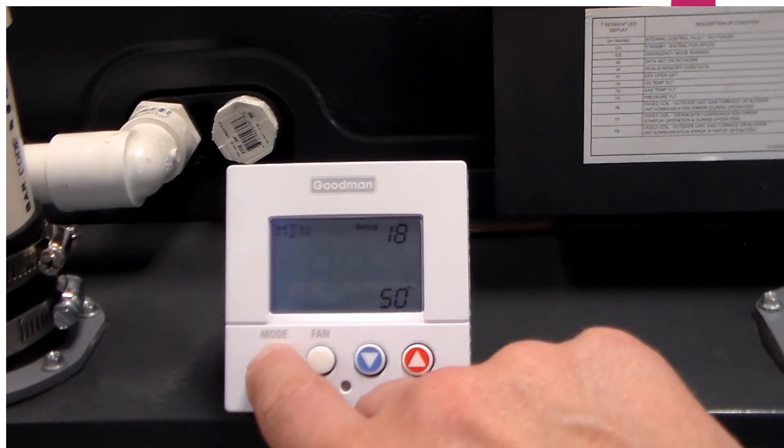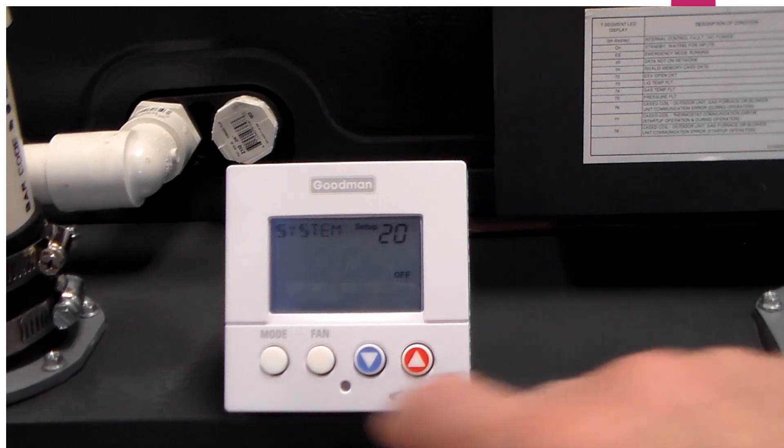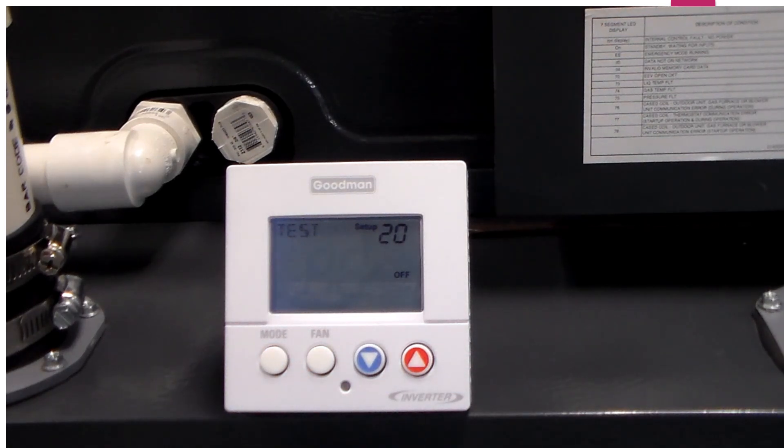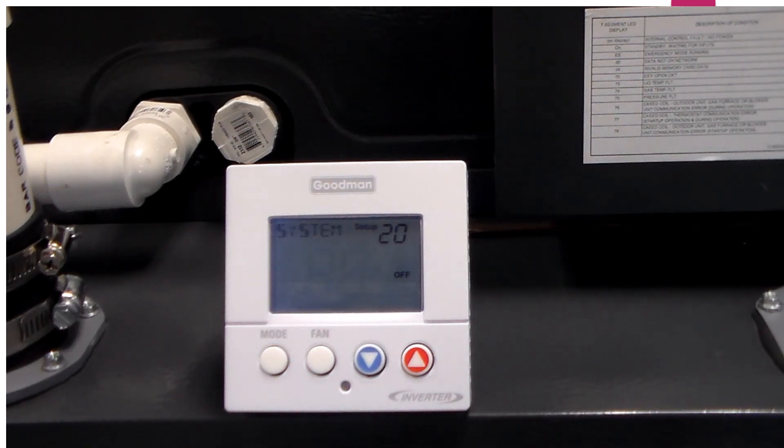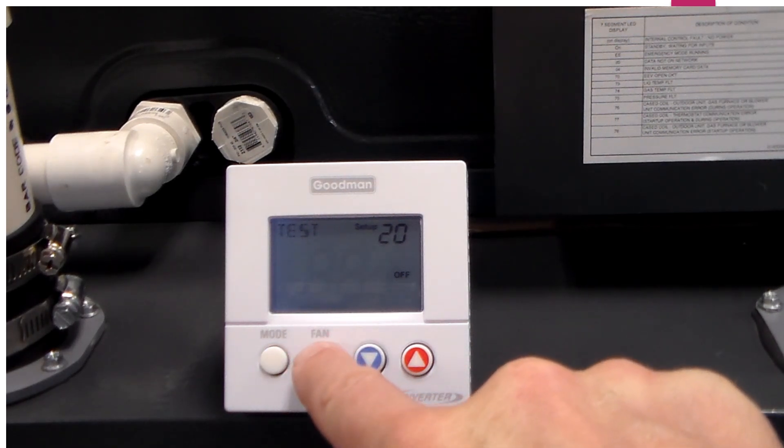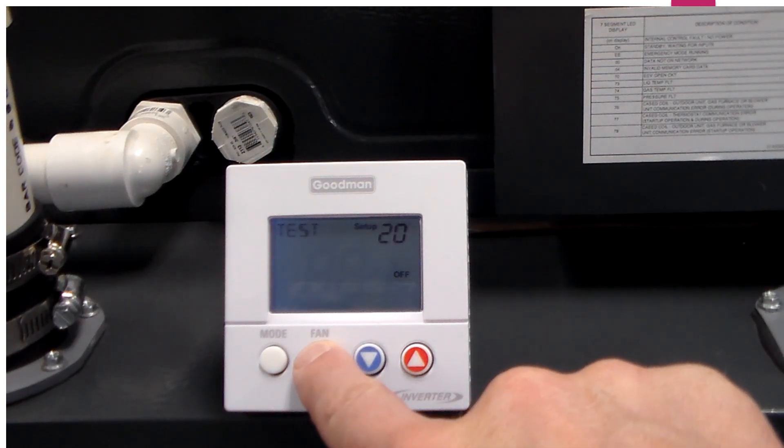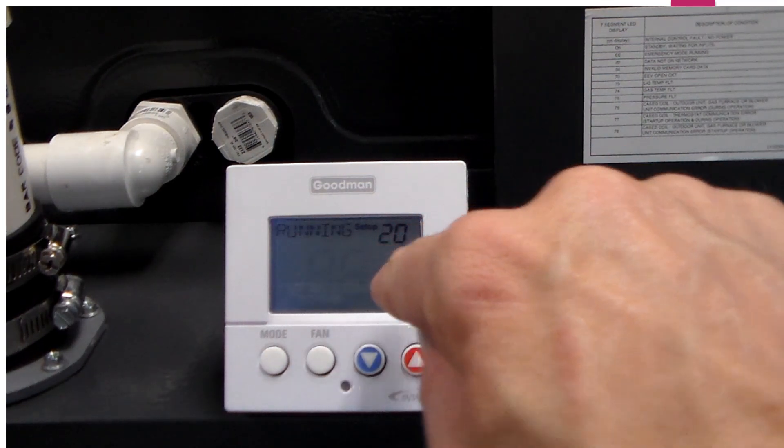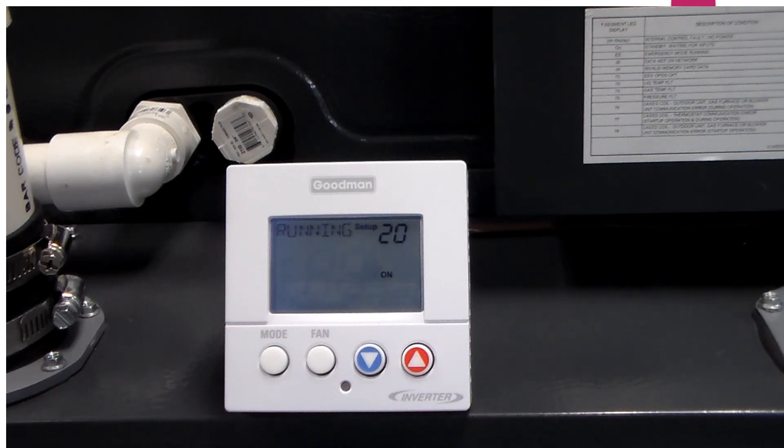Mode number 20 is my test mode. Once I hit mode number 20, I can go ahead and hit the fan button for two seconds. And now it will switch from off to on. And now I am running in the test mode.